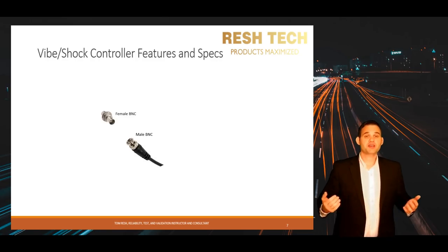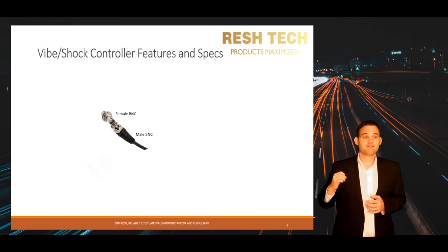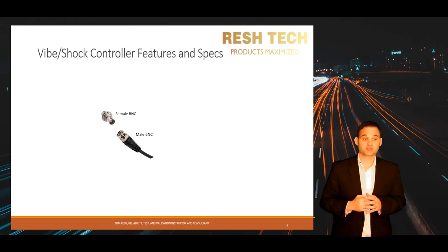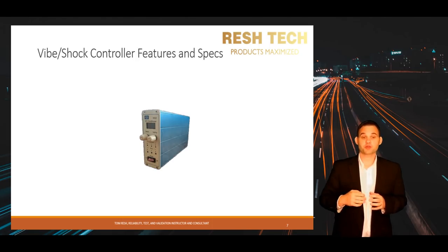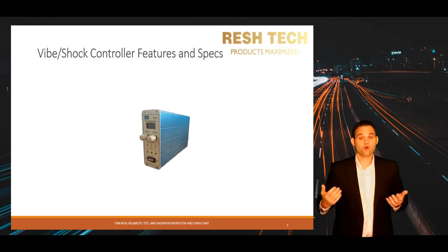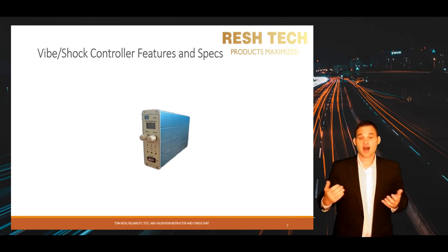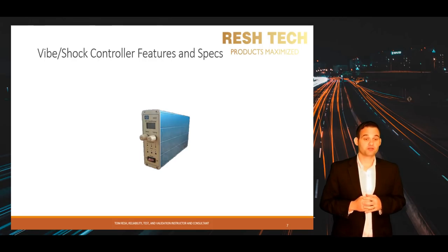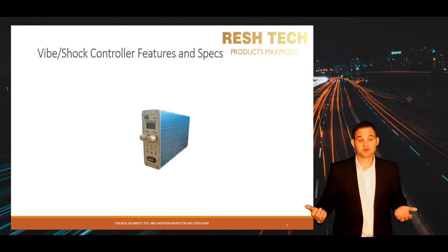The accelerometer inputs on a vibration controller usually have a female BNC. You can purchase accelerometer cables with a BNC male connector on one end, or purchase an adapter that goes from 10-32 accelerometer connectors to male BNC. Most current vibe controllers have a built-in integrated circuit piezoelectric power supply — or ICP power supply — for voltage mode accelerometers.